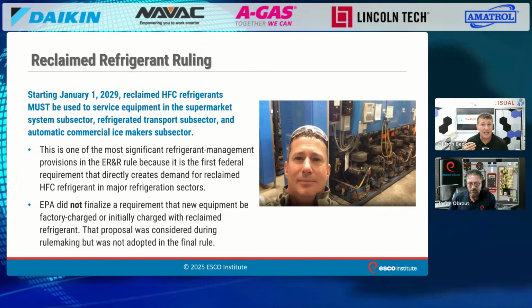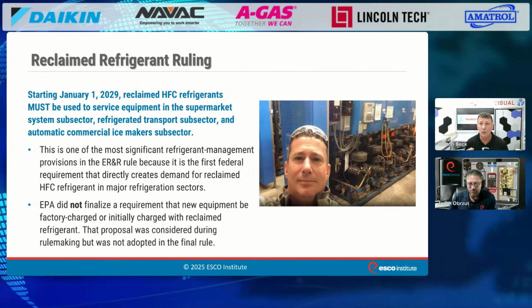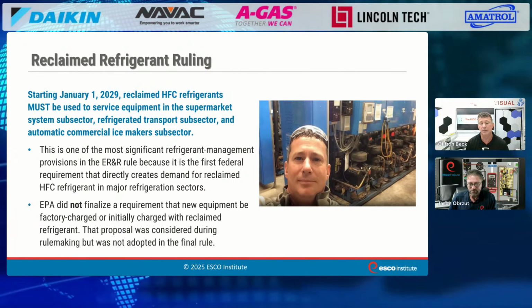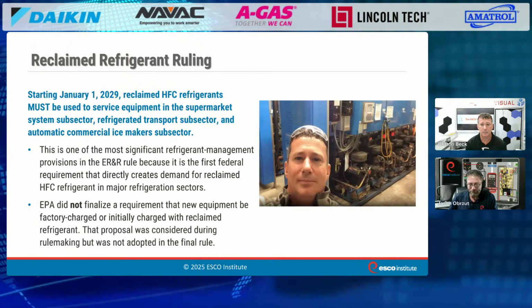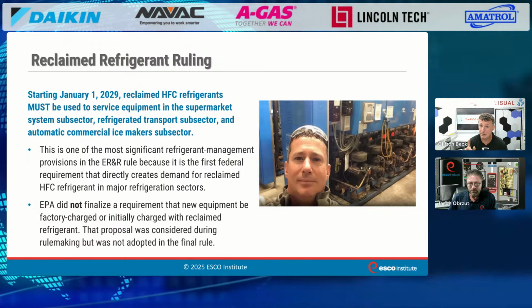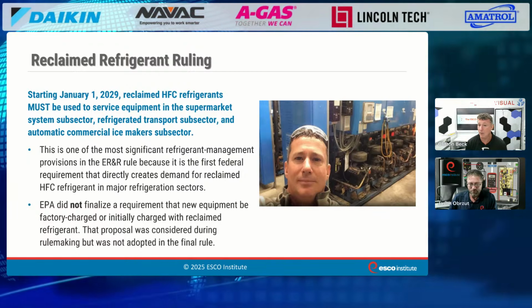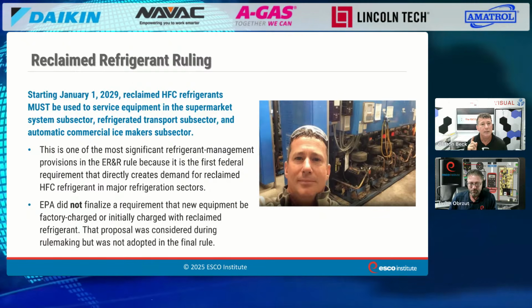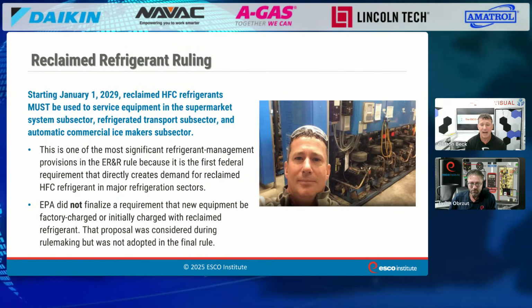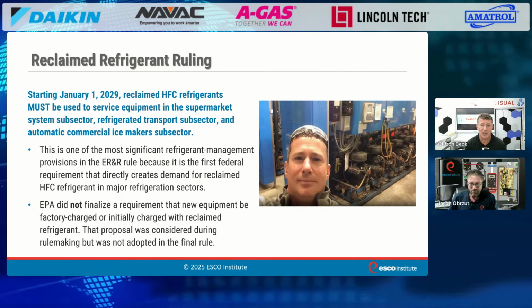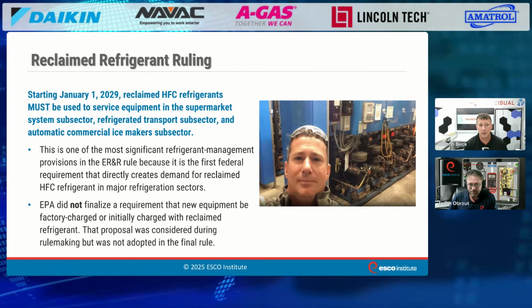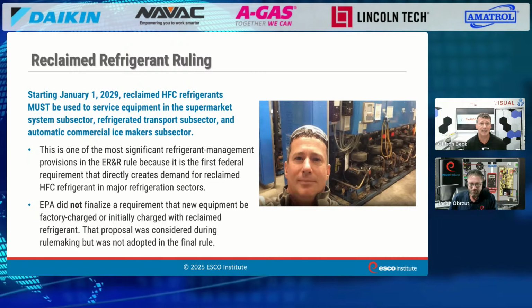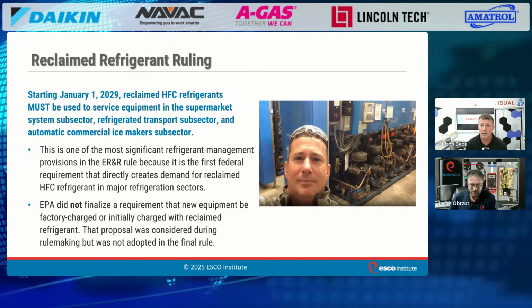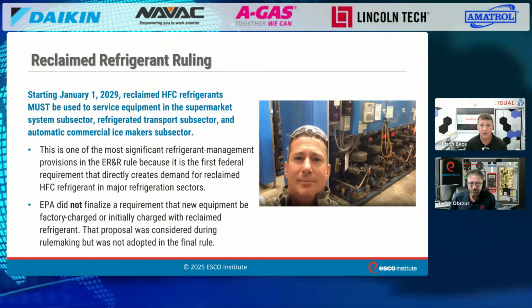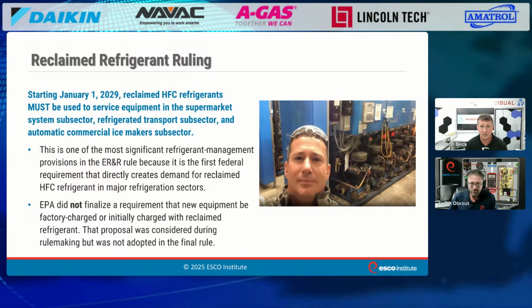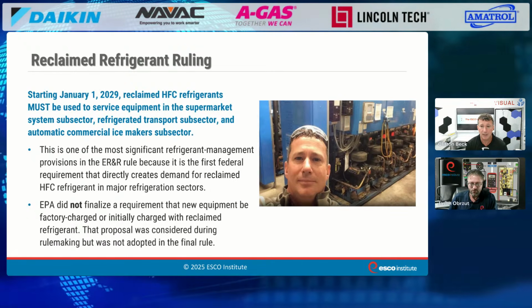Now we have to focus on this - it's so important because we are going to start losing our supply of virgin refrigerant for working on systems. It's a fact. We almost had it in our residential and commercial applications, but that was not put into the process. Starting January 1st of 2029, that's going to be the most significant change for service gas as we go into the supermarket subsector, the refrigerated transport subsector, and automatic commercial ice machine subsector. You're not going to be able to use virgin HFC refrigerants for servicing those things - you'll only be able to use reclaimed gas.